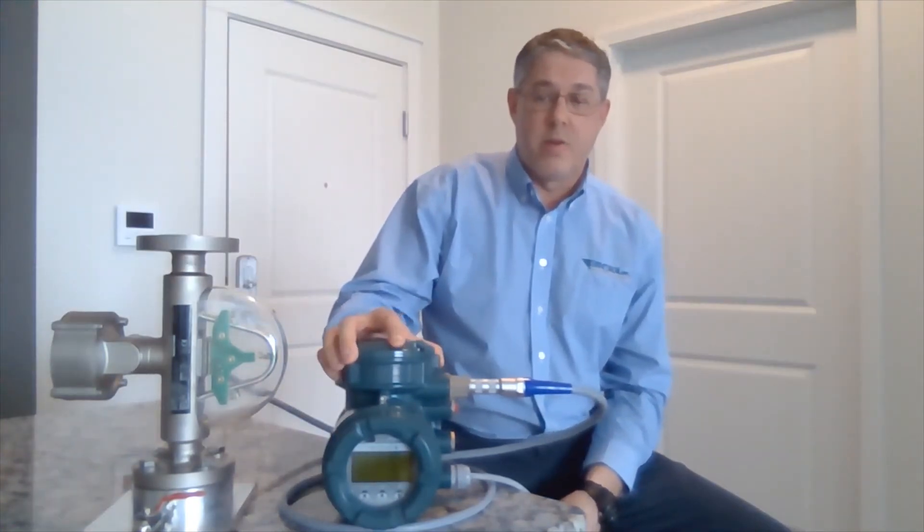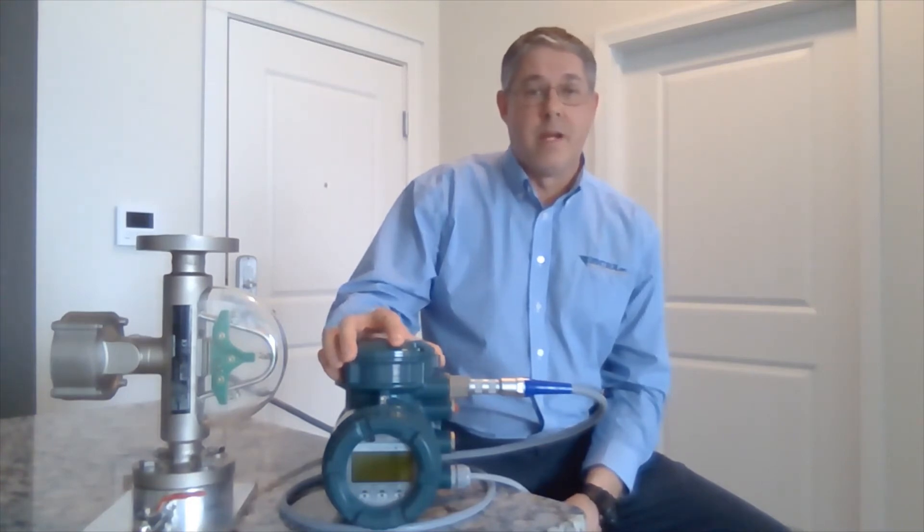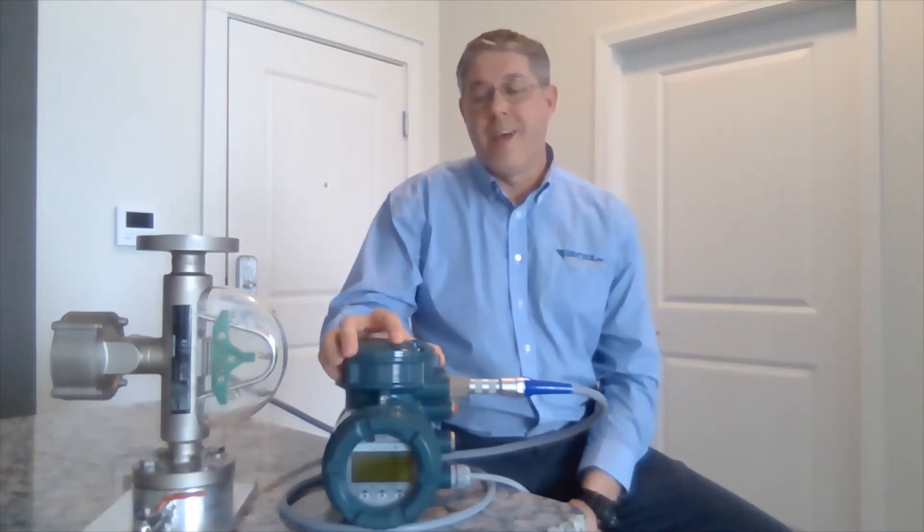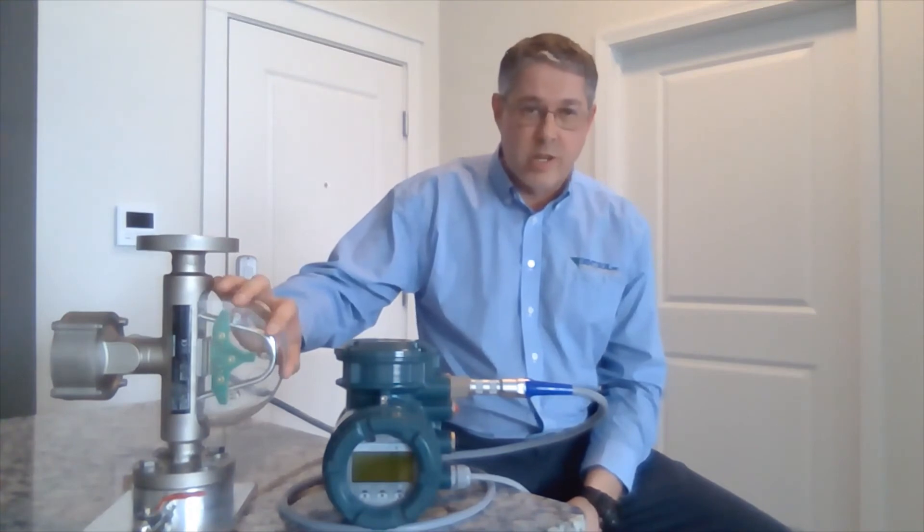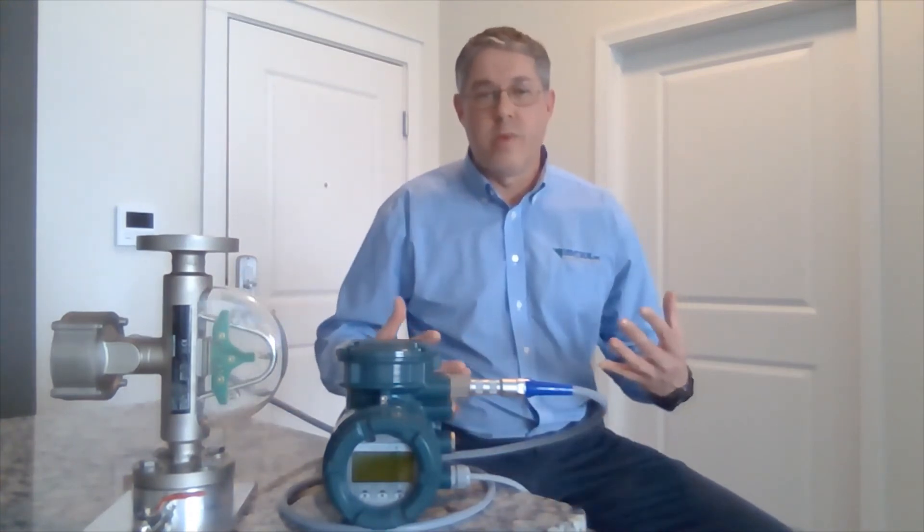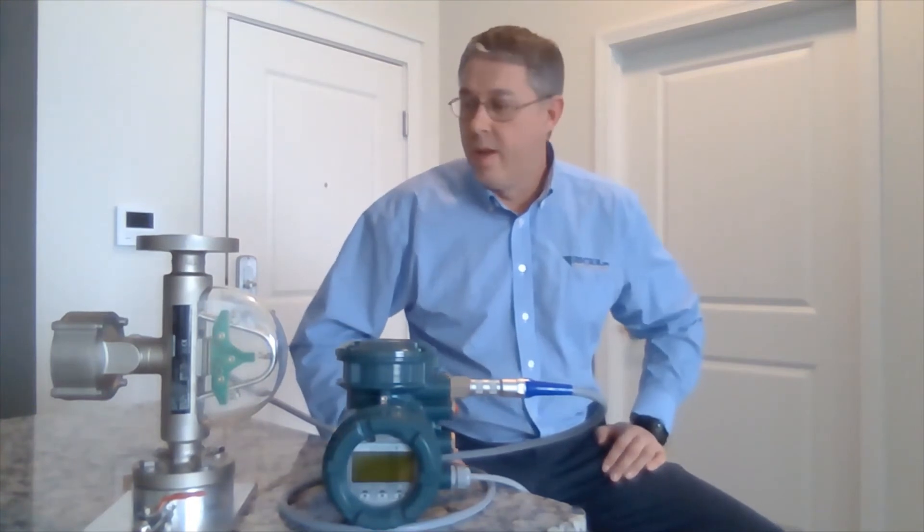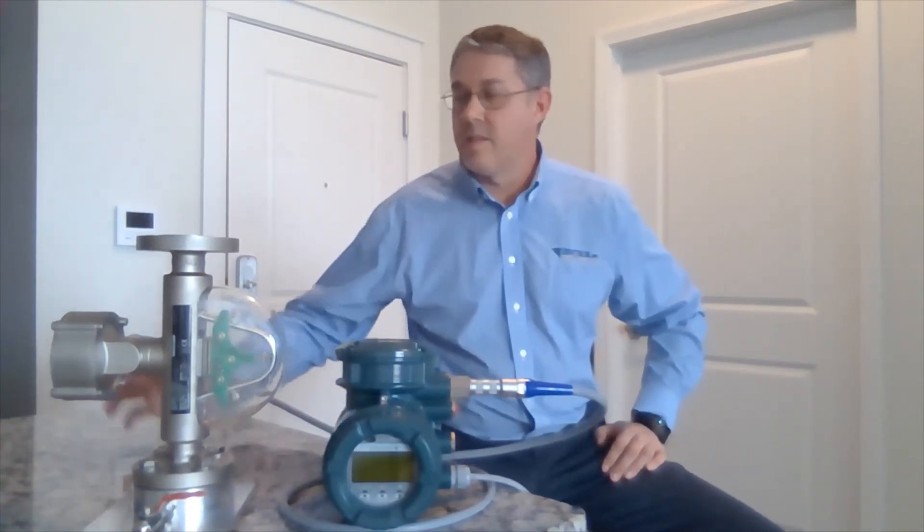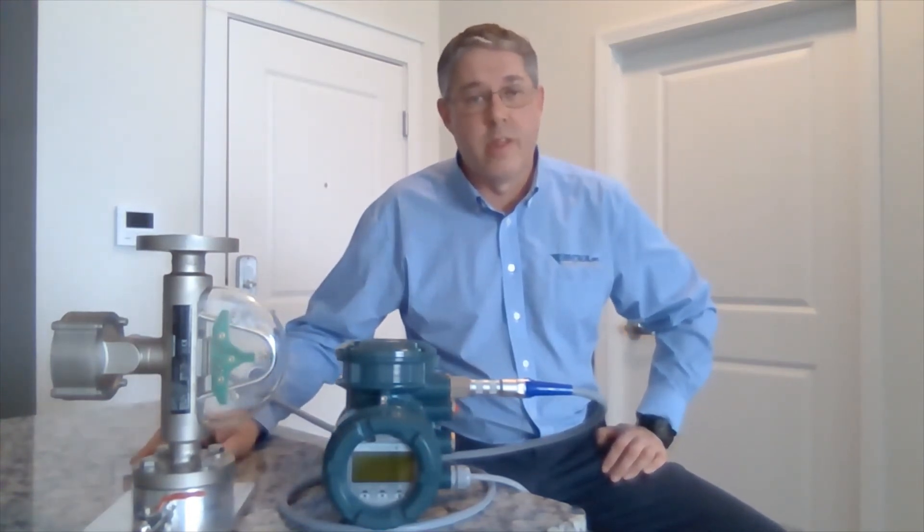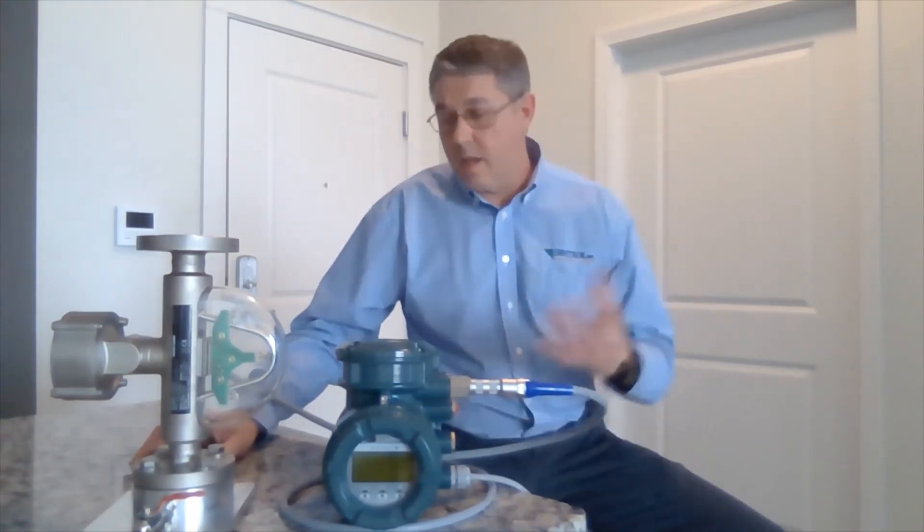The really nice thing about the Rotamass TI products is it has something called a total health or a total tube check function. This is the function where the meter will run through a verification and a tube integrity program. This basically tells us if the meter is still operating within manufacturer's specifications, and it can extend the life of the calibration of the unit.